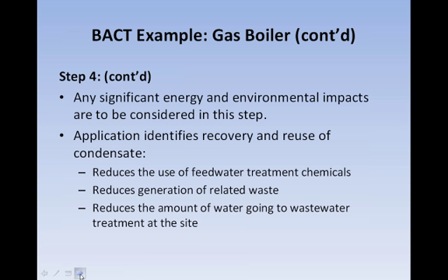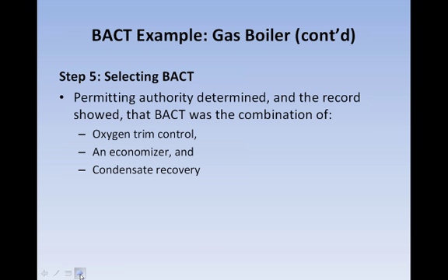Any significant energy and environmental impacts are to be considered in this step as well. The application identified recovery and reuse of condensate as having a number of environmental benefits. One, it would reduce the use of feedwater treatment chemicals. It would also reduce generation of related waste, and it would reduce the amount of water going to the wastewater treatment at the site. This information provided additional support for the condensate recovery as part of the BACT determination. So the permitting authority determined, and the record showed, that the BACT was a combination of oxygen trim control, an economizer, and the condensate recovery.